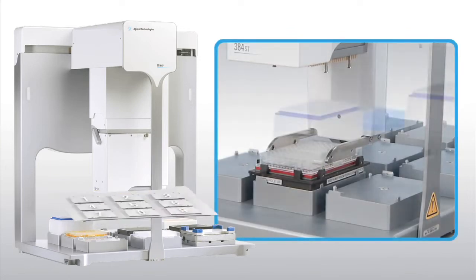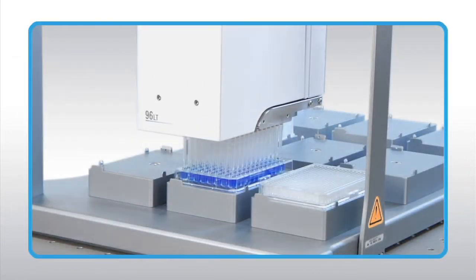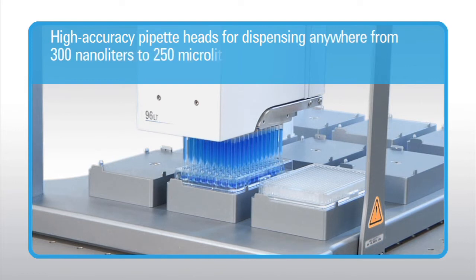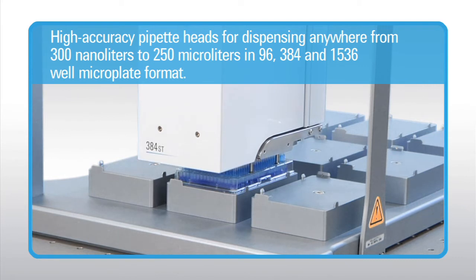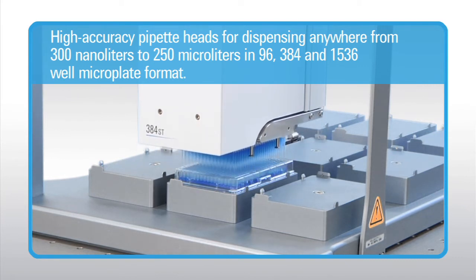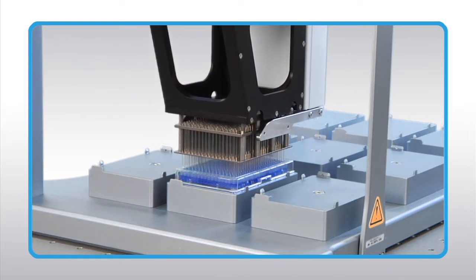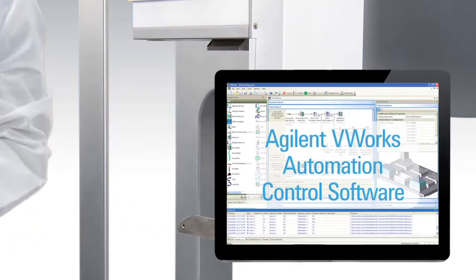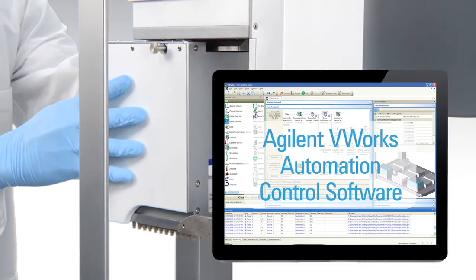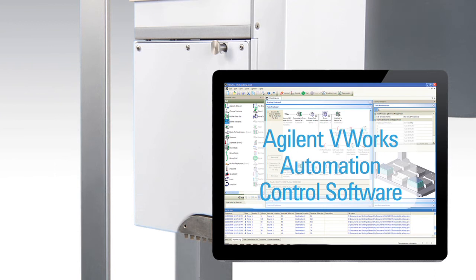Each of the Bravo's nine deck positions can be customized to add the additional on-deck functionality required for your workflows. The Bravo platform uses proven high-accuracy pipette heads for dispensing anywhere from 300 nanoliters to 250 microliters in 96, 384, and 1536 well microplate formats. Pin tool transfer heads can also be fitted onto the Bravo for sub-microliter liquid transfers. Pipette heads can be changed in seconds and are automatically recognized by the VWorks software.